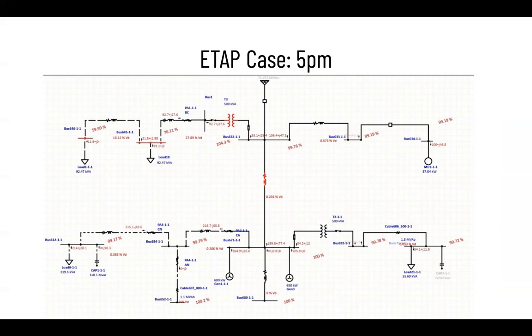However, during this time, when the PV is delivering 105 kilowatts and our battery source is delivering 364.9 kilowatts, there aren't many problems with our cables or our transformers. The only issue that we did come across during this analysis was in our residential area, which is the top left. We did have low power factor percentages. We had a low voltage. I mean, we had voltage droppage.